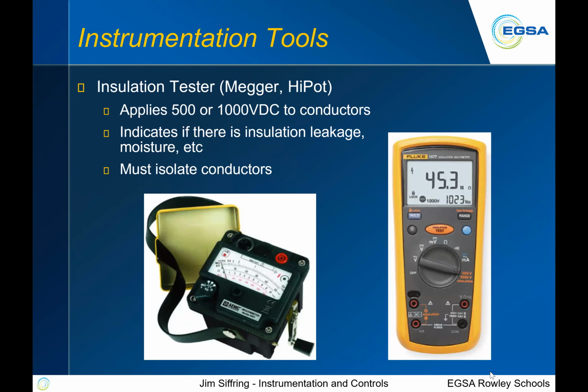Instrumentation tools, also a Megger insulation tester, Megger, a HiPot, sometimes they're called, things like that. What this device does is applies a voltage to conductors, and you're looking for any kind of current flow between conductors. So if there's any kind of insulation leakage, these things will find it. There is a little bit of skill to operating one of these things. You have to have some training, some knowledge of what you're doing there. But this is one of those service tools that you really need to have if you're doing quarterly or annual maintenance on a generator set, especially in a standby application.